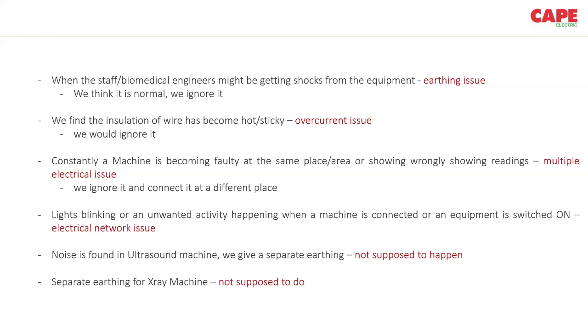Then there would be some unwanted activities happening when an equipment is connected. Like maybe if we have connected an equipment, the lights would start blinking in an OT. Maybe if we connect a cautery machine, the OT lights would blink. Or some other equipment might show some blinking or switch off. Or even in case of an ultrasound machine, some noise can be found. We'll think that it is due to earthing. It is not supposed to happen because we are connecting a 3-pin cord to the plug socket, right? So if earthing is not proper, all of these things will happen. So all of these are electrical issues and we'll think that it is a common problem.